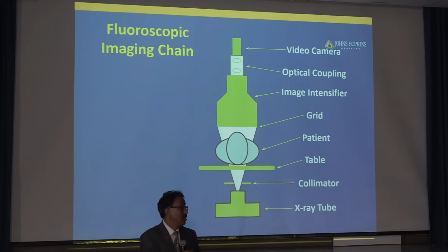This is one of the workhorses of fluoroscopy systems in any hospital around the world. The X-ray tube is under the table, with the image intensifier on top. These are lead skirts to protect the user standing next to it from scatter radiation. And they view the images on a computer screen or a TV camera. That's pretty much the workhorse of any fluoroscopy department in the world. Now you move on to interventional fluoroscopy, like cardiology or interventional radiology. You have these C-arms. They are not restricted by the table, because the setup allows you to rotate in any direction you want. This is a biplane system. It has two different systems, so you can simultaneously image a patient while you are positioning a stent or a catheter, or doing a stent embolization, everything.